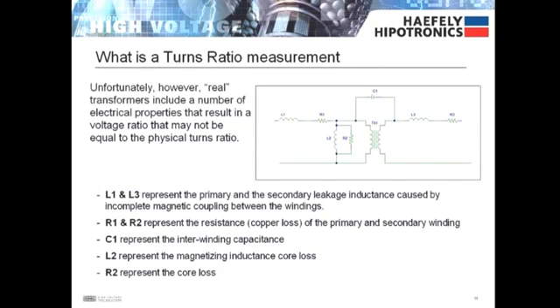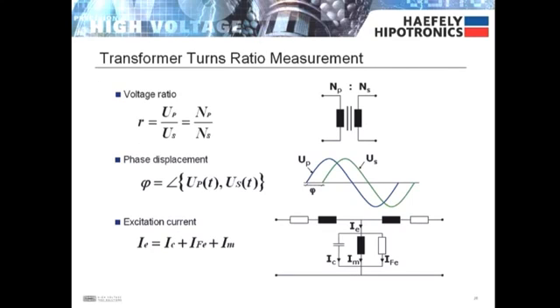Unfortunately, however, real transformers act as a complex RLC circuit with losses that result in a voltage ratio that may not equal the physical turns ratio. In addition to turns ratio, the 2293 can measure voltage ratio, phase displacement, and excitation current.